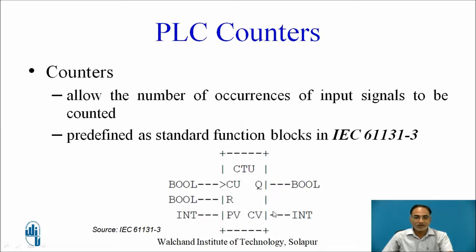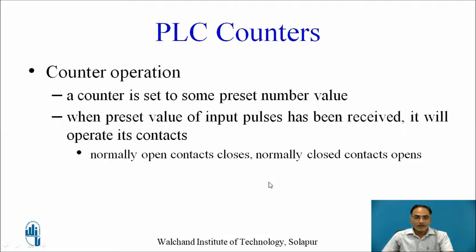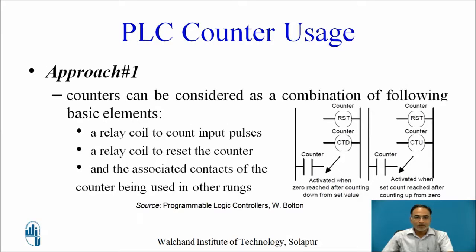A counter is set to some preset value represented as an integer. When the preset number of input pulses have been received, it will operate its contact — meaning a normally open contact will close, whereas a normally closed contact will open. There are two approaches to how you can use a counter.